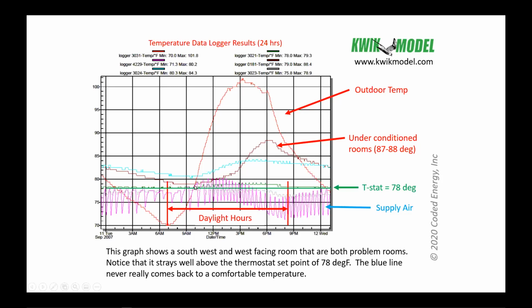When it goes back up, it's off. So on, off, on, off, on, off, on, off, on, off, on, off. Look at all these spikes. That is a classic example of short cycling. And look at the outdoor temperature: it's well above the design temperature of 99 degrees.